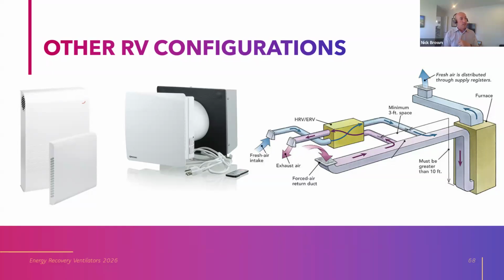And what's funny about these is one will be running in exhaust and its pair unit will be running in supply mode. So in that way, they're balanced. And then they switch direction, and then they switch direction another minute later. So every minute, roughly, they're switching direction, and that ceramic core has thermal mass to it. And that's how they, in effect, temper the incoming fresh air. Pretty funky design. They're only up to like 20 CFM, so you'd need pairs in rooms all over your house. But another interesting approach that doesn't require ducting.